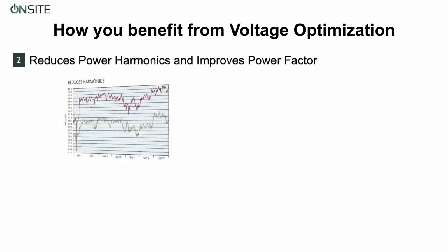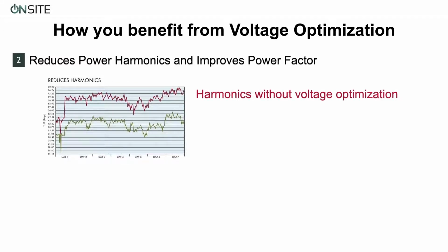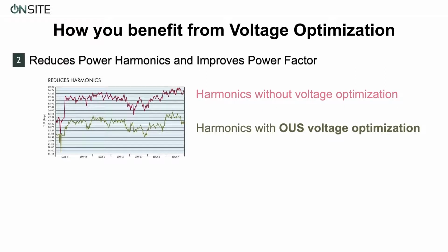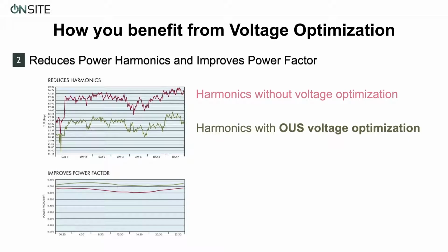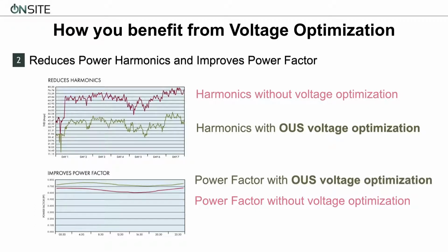Another way that you can benefit from voltage optimization is the reduction of power harmonics while improving power factor ratings. Here's a before and an after chart showing improved harmonics as a result of using Onsite Utility Services voltage optimization. And here we have an example of how Onsite Utility Services voltage optimization contributes to improving the power factor. Where there is high fluctuating voltage and high consumption of electricity, power factor correction equipment should be used along with Onsite Utility Services voltage optimization.